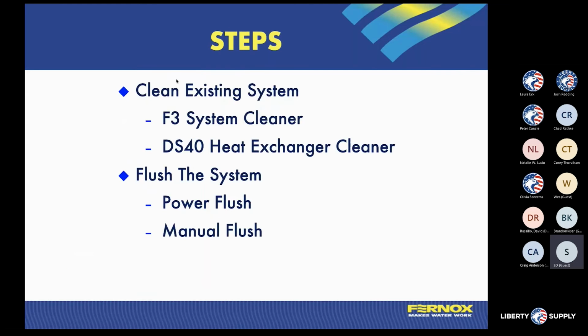So obviously we're going to look at cleaning the system. We have a system cleaner, which is a detergent style cleaner. And then if we have a plugged up heat exchanger, we have a more aggressive acidic cleaner. The difference is we do not put our DS40 descaling agent in a whole system just because of how aggressive that is. We would just use our F3 detergent cleaner to get most of that debris and sludge that's in the system and have that be pushed into solution. So when we do flush it down, you're getting as much of that debris out of that system.